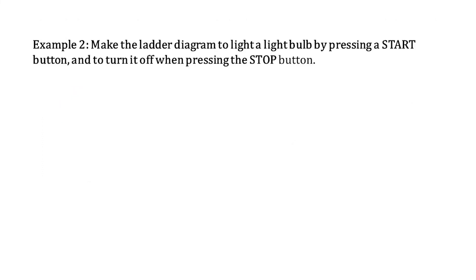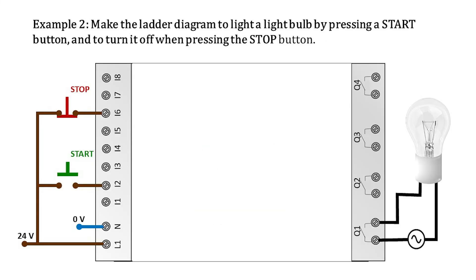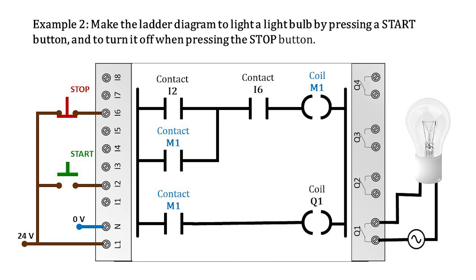Now let's see a second example: make the ladder diagram to turn on a light bulb when pressing a start button, and turn it off when pressing the stop button. The start button will be considered as normally open and the stop button as normally closed. The start button will be connected to input I2, the stop button to input I6, and the bulb to output Q1. This would be the ladder diagram for this example. Coil M1 and contacts M1 are memories, which are internal variables.